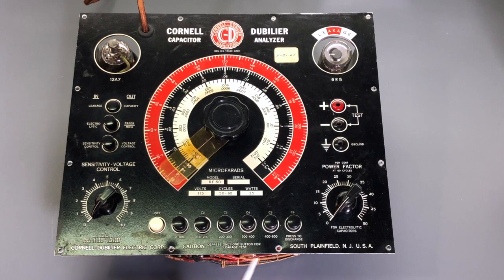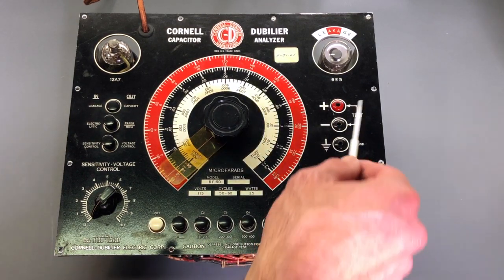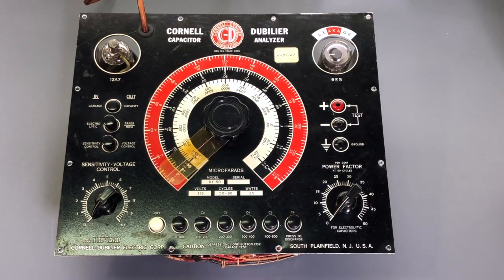On a tester of this age, I don't think the voltage will be spot on at 100 to 200, but certainly it should be within that range as this control is adjusted. You wouldn't want to see, for example, 400 volts being applied over here when you're in the 100 to 200 range. A high voltage over here could damage a capacitor if you weren't expecting that kind of voltage.